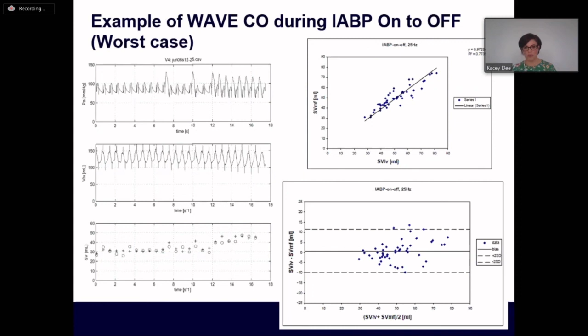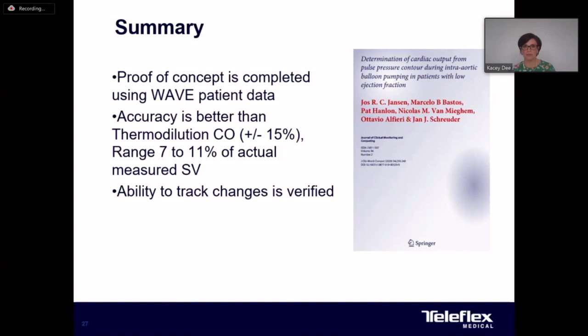So we conclude that the model for calculating stroke volume and cardiac output is feasible with our catheters and our wave calculations, and within the accepted accuracy range of thermodilution of plus minus 15%. Now, the algorithm faithfully follows the change in stroke volume, which may be more important than accuracy of the readings themselves. And this method will allow the monitoring of stroke volume and cardiac output, along with patient hemodynamic pressures using the balloon pump and the catheter without any other devices from the start of therapy. Now, this will provide a quantitative set of information for clinicians to determine if the patient is a responder to balloon pump therapy or if we require escalation of MCS therapies.